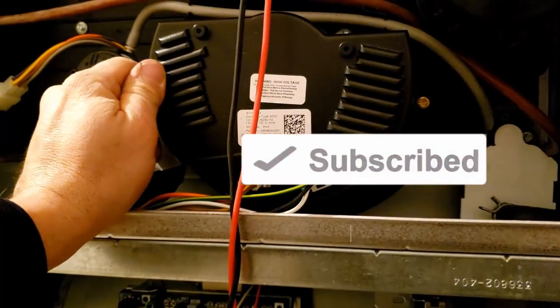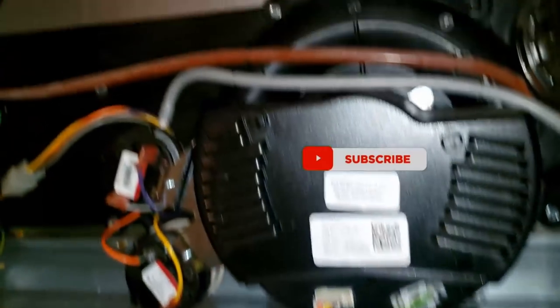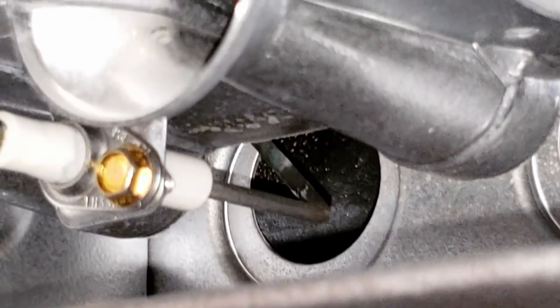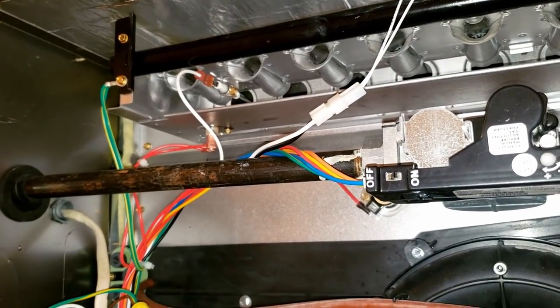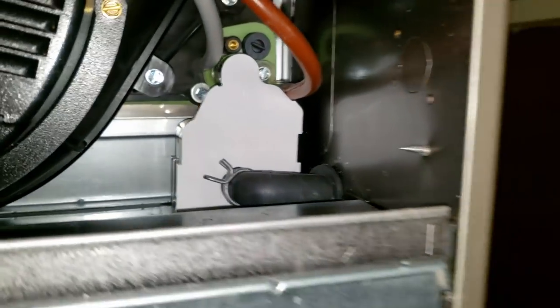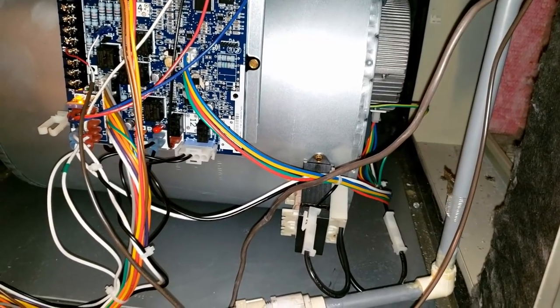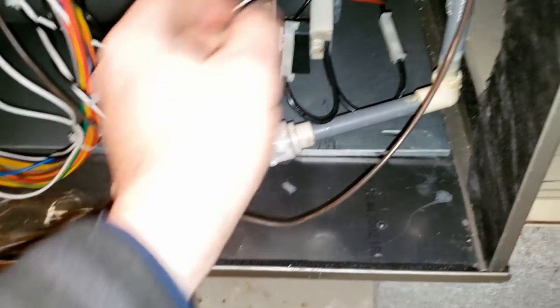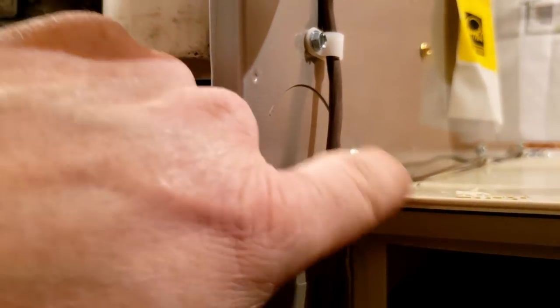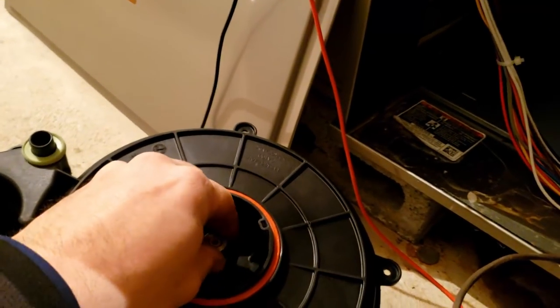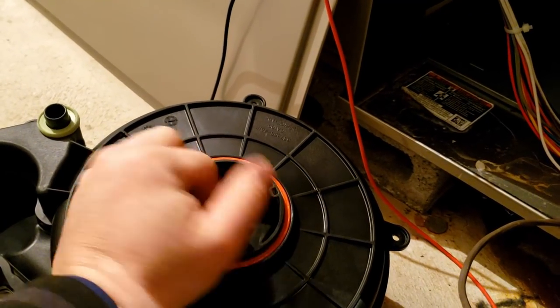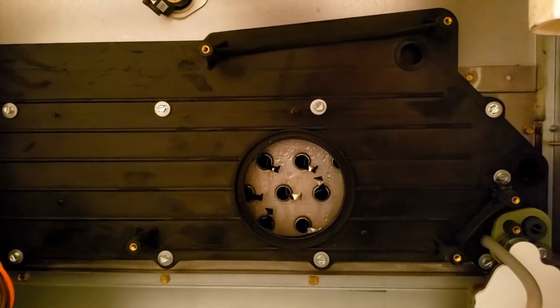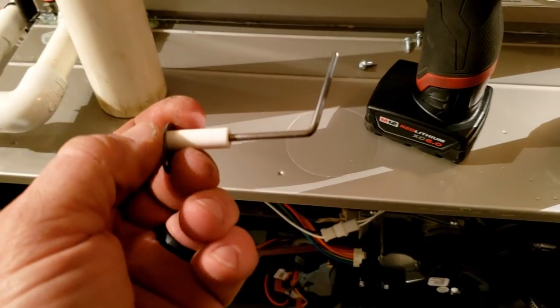Alright, so I'm down here in a basement - it's at no reception. Notice the flame sensor looks a little cruddy, so we're gonna go ahead and clean that up too before we forget. And then probably clean out that condensate trap as usual. I might see if I can't get us a hose of some sort to kind of make this thing work a little bit better. This would be a lot nicer if it had a clamp on that with a hose and then this would be flexible. Now you've got to love when the guys run zip screws into that - they're so nice and sharp when you're trying to grab a hold of that to get that pipe off. You gotta be careful of that. So the motor spins freely, nothing stopping it from spinning. So unfortunately it looks to me like we're going to go get a draft motor. So go ahead and get that on. Get a call in, let's see if they've got it. Got the flame sensor cleaned up.